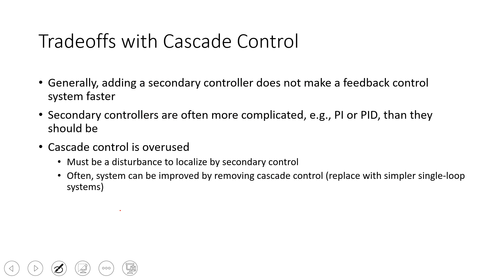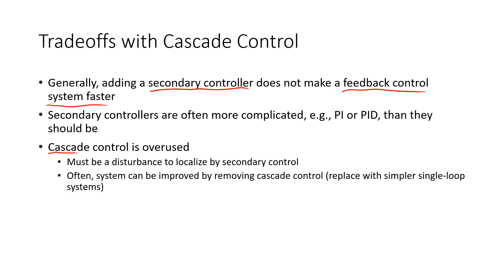Here are some trade-offs or misconceptions — problems with cascade controllers. Generally, adding this secondary controller does not make the feedback control system faster. It's just going to reject frequent disturbances that might be affecting the process. Also, the secondary controllers are often more complicated. Once you start adding cascade layers, this whole feedback control often becomes much more difficult to maintain and tune — that's just an added layer of complexity. Cascade control tends to be overused. We tend to build in complexity as different events happen in control systems, and it's easier to add things than to take them out. Sometimes a system can actually be improved by just removing these layers of cascade control with simpler single-loop systems.